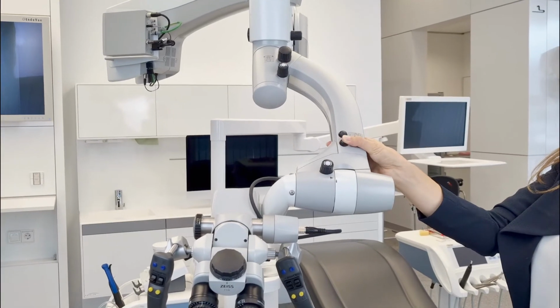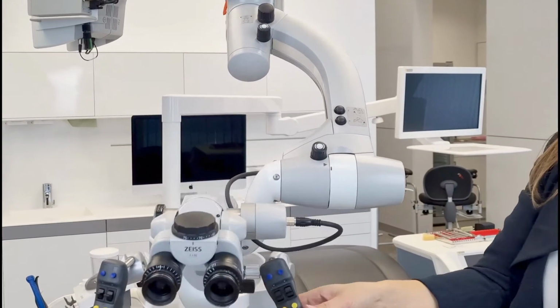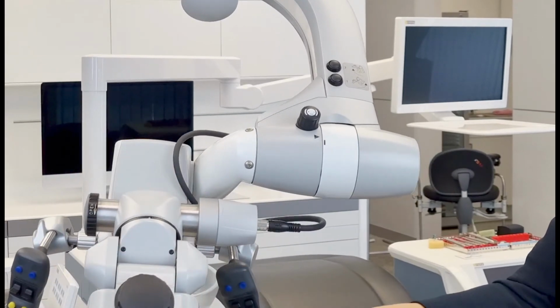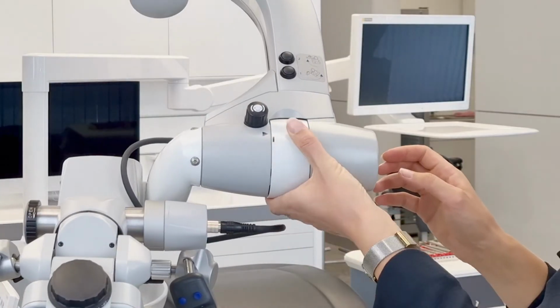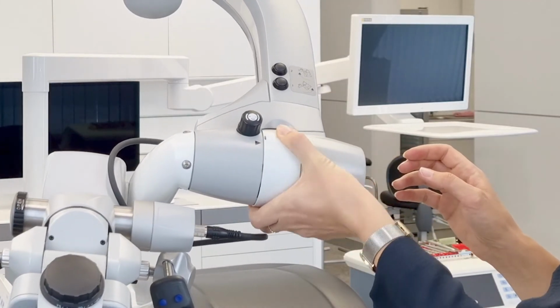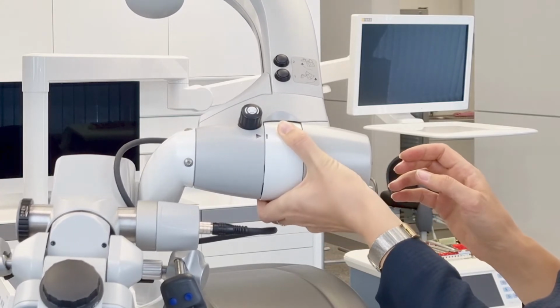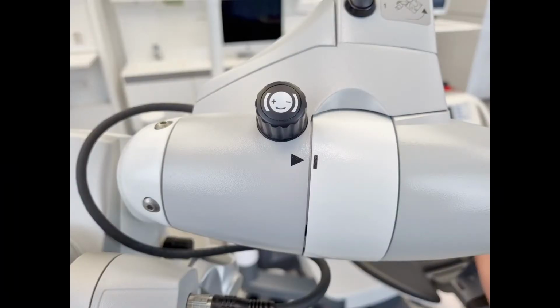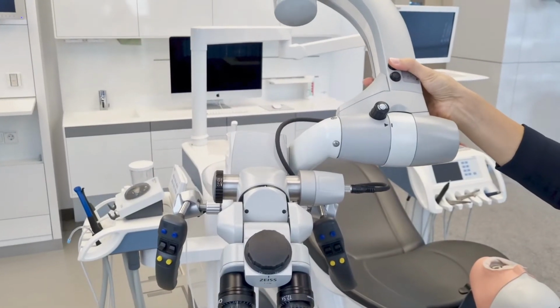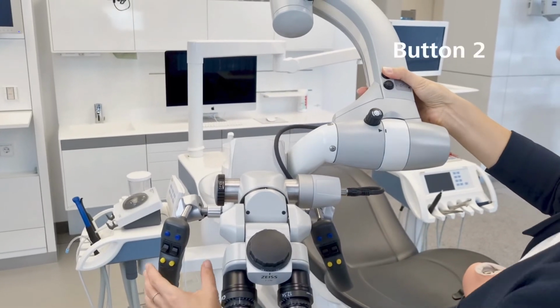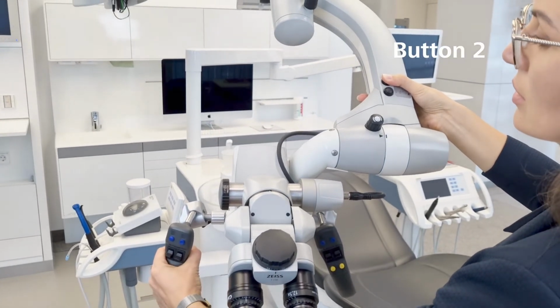In that case, the white ring with the marking does not move when you turn the surgical microscope. Check whether the white ring is in its 0 position. If this is not the case, turn it manually to the 0 position and align the black arrow with the black line. Leave the surgical microscope in its center of gravity position and press button 2.